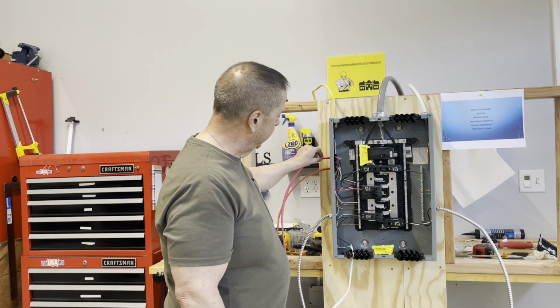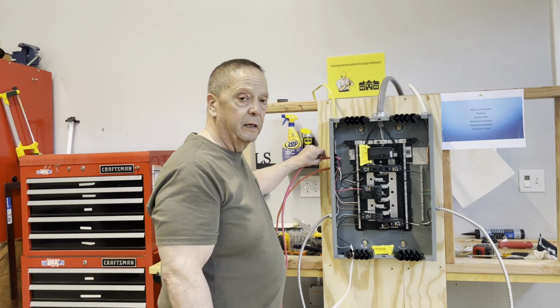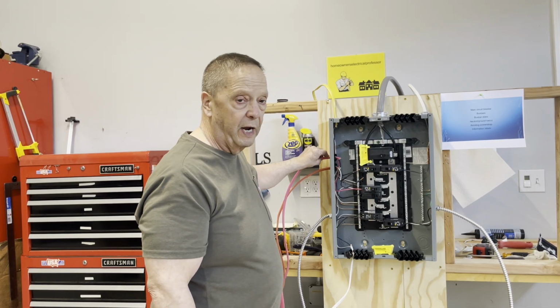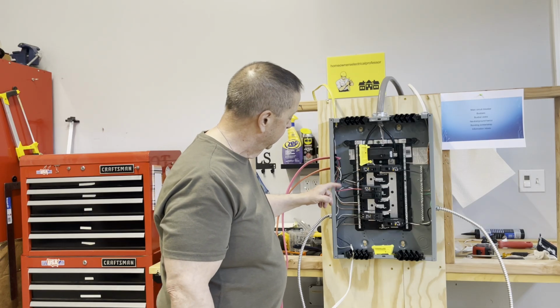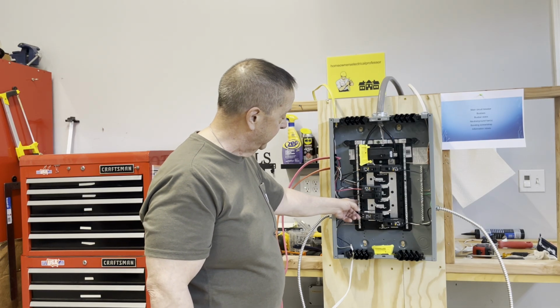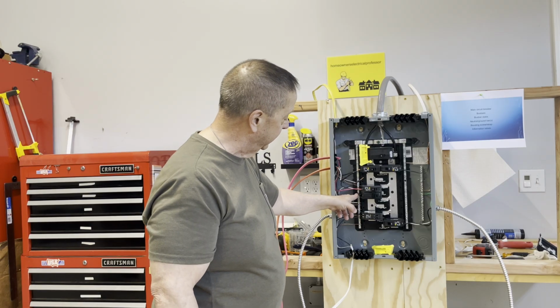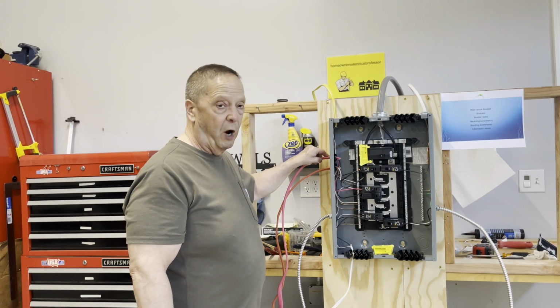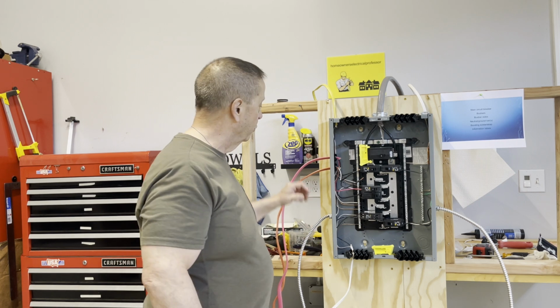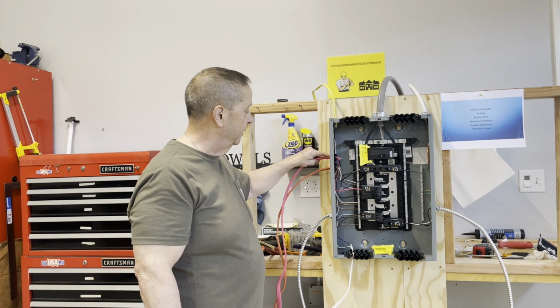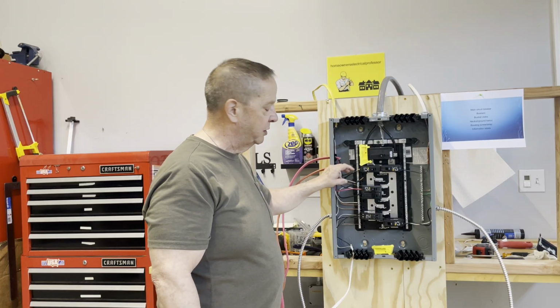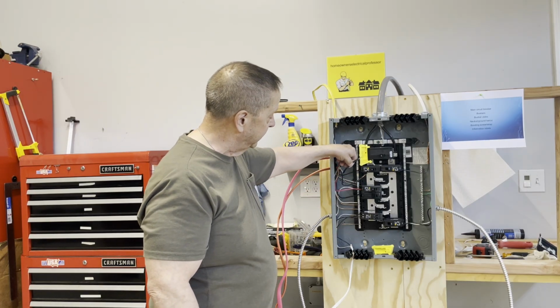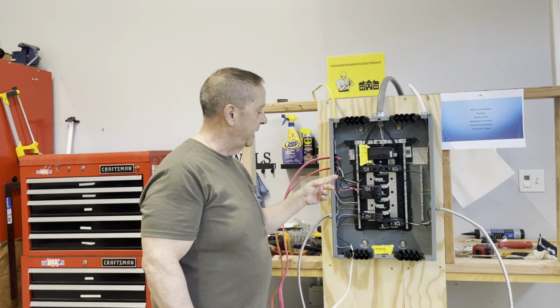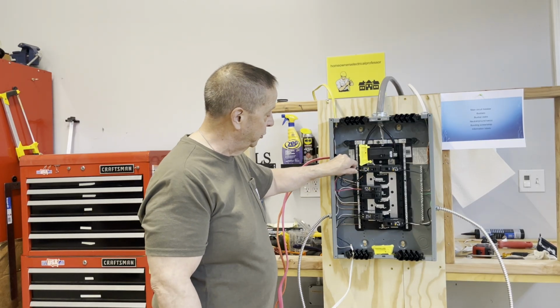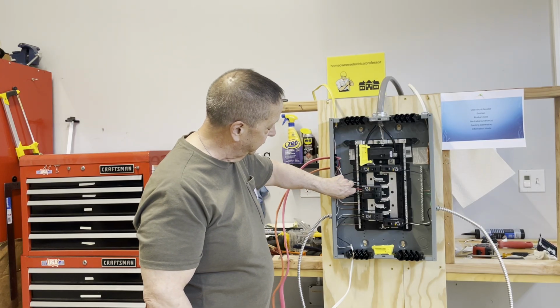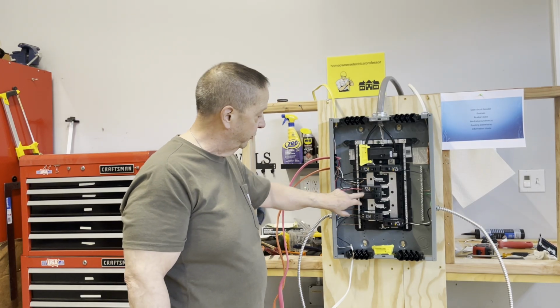I brought in a 10-3 NM cable, which has a black, red, white, and a ground wire. The white and the ground terminate on the ground bar. The black and the red terminate here. Most dryers today and some wall ovens will require that third wire. Now, air conditioners are normally just a straight 240, and you are allowed to take the white wire and tape it black when all you're doing is using 240. In that case, these two conductors would terminate on the 2-pole 30 amp breaker.